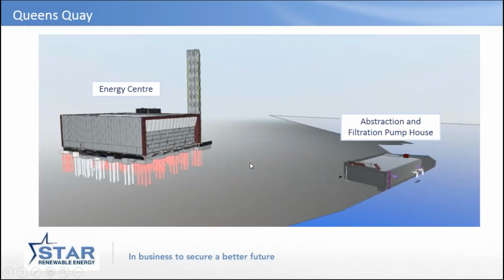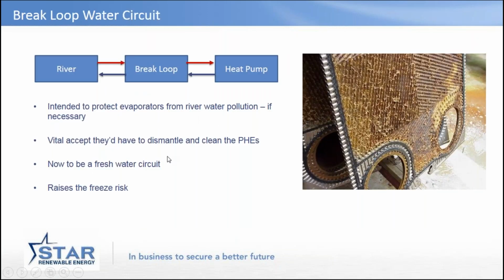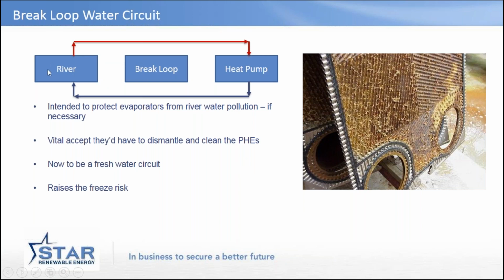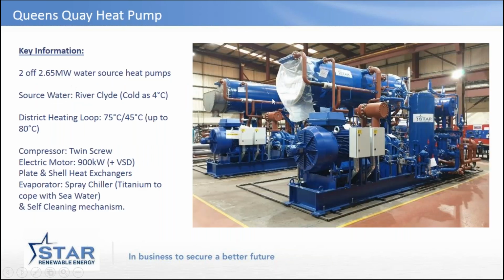It's easy to harvest. So we've got a pumping station next to the river and the energy centre over here. One of the ways that we do it in particular is not to have a break loop. The challenge with working with rivers is they really aren't terribly clean, and putting in a break loop just exacerbates the problem. What we actually do is get rid of the break loop and take the river water direct into the heat pump. So we don't use plate heat exchangers as that primary point of contact between the river and the heat pump. We use tubular heat exchangers that you can clean. There you see them, the horizontal vessels. They take the river water directly in through them and out, and there are little brushes inside these tubes that can be pushed upwards or downwards by reversing the flow of water, and that gives us the cleaning capability.